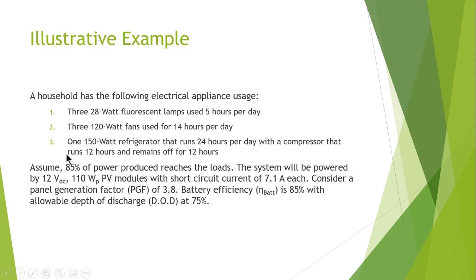It is given that 85% of the power reaches the load, and the system will be powered by 12-volt DC. A 110-watt photovoltaic module with a short-circuit current of 7.1 amperes each should be considered, and assume a Panel Generation Factor of 3.8.